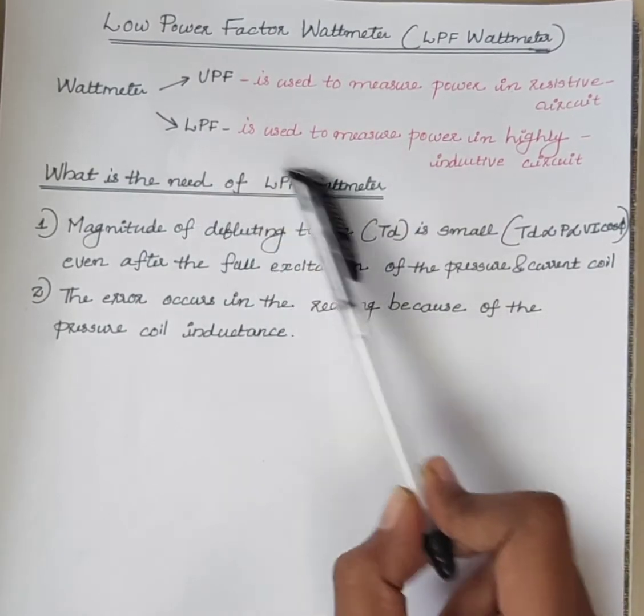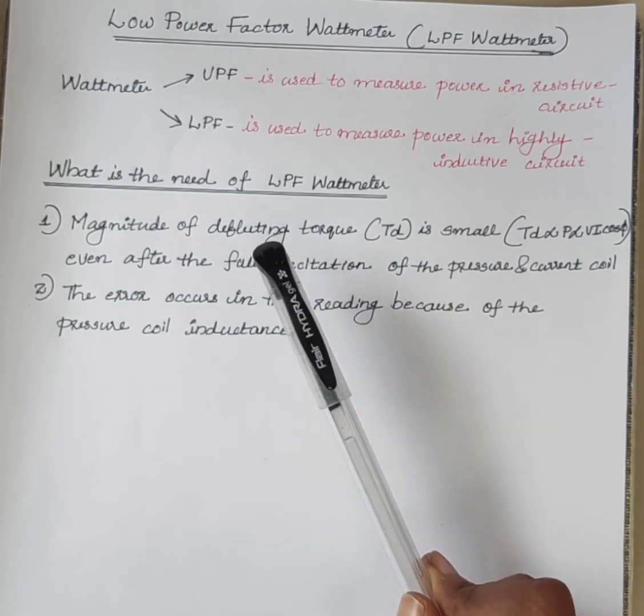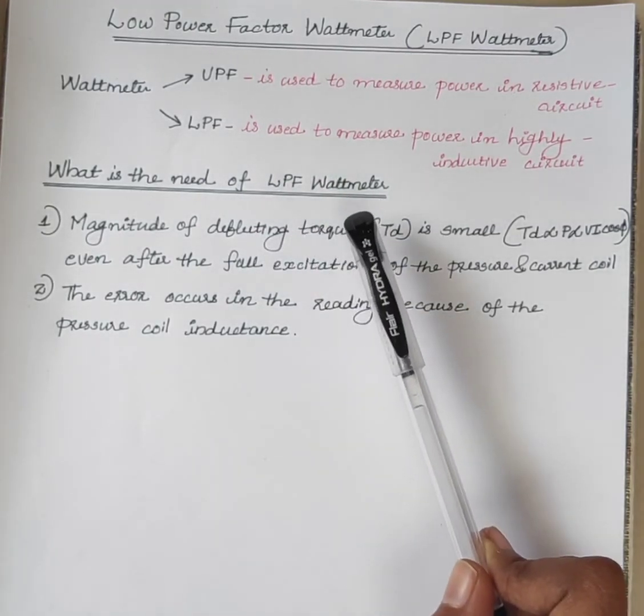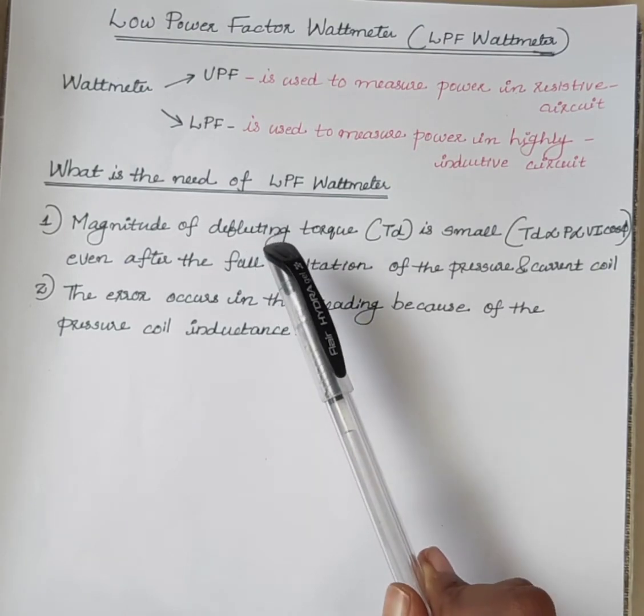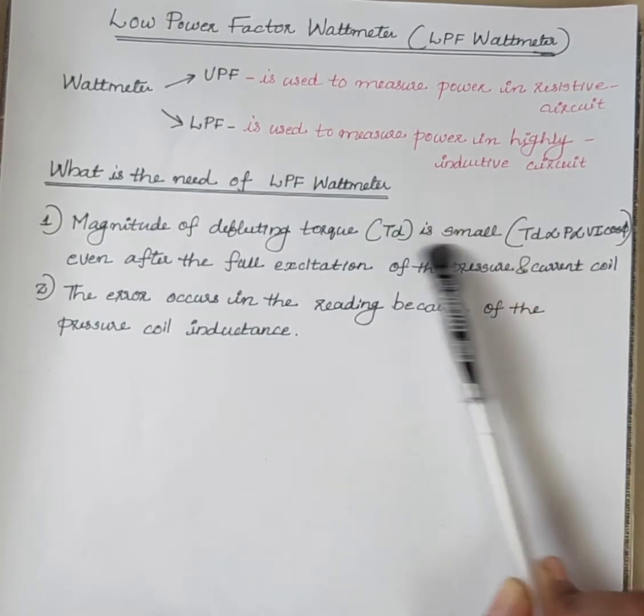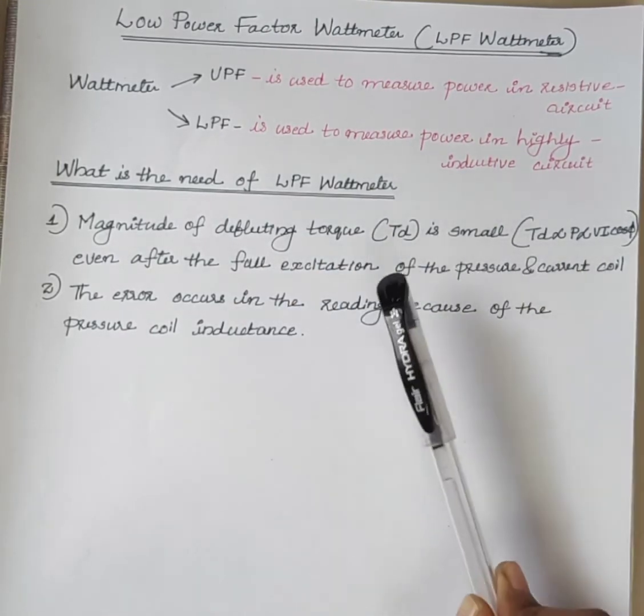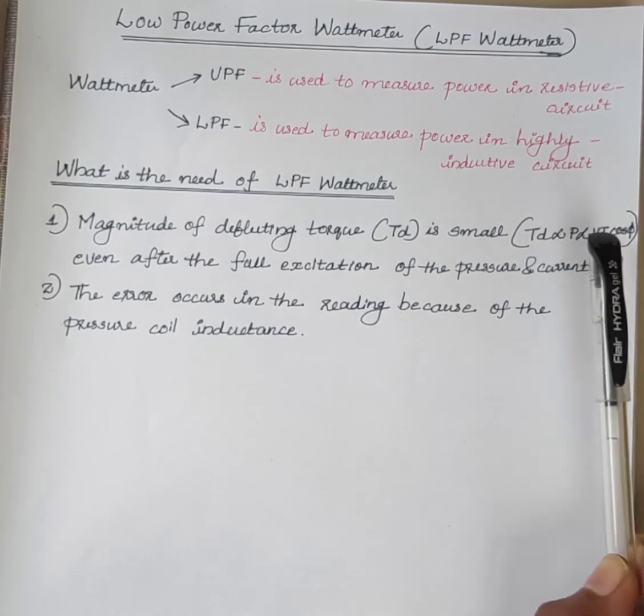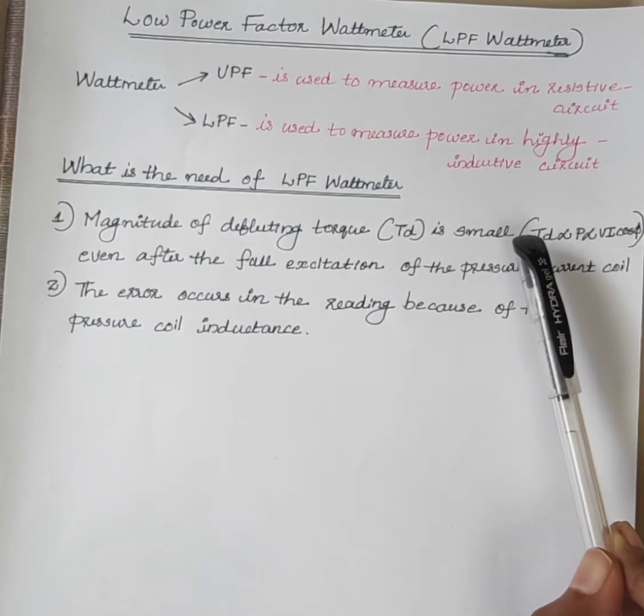So, what is the need of LPF watt meter? If we are using an ordinary watt meter for measuring low power factor, it gives inaccurate results. This happens because of two reasons. First, if we are using an ordinary watt meter in a highly inductive circuit, the magnitude of deflecting torque is very small, even if we are applying full excitation to the pressure coil and current coil. Because the deflecting torque of the watt meter is proportional to power, and power is proportional to VI cos phi. If the power factor is low, the deflecting torque is also small.